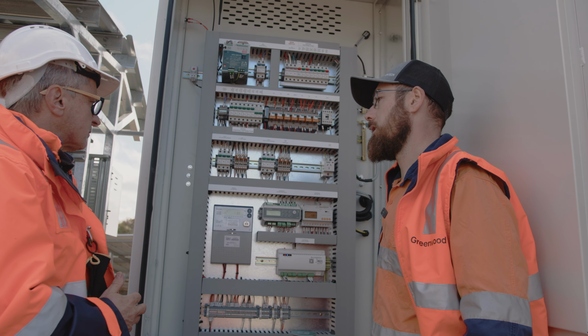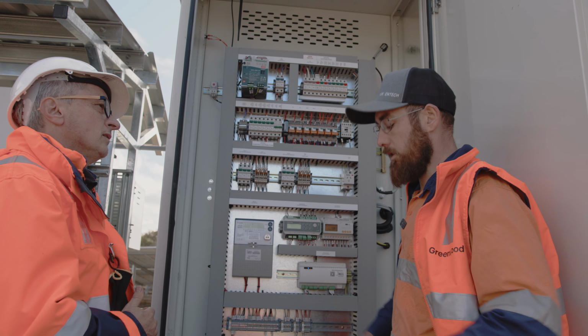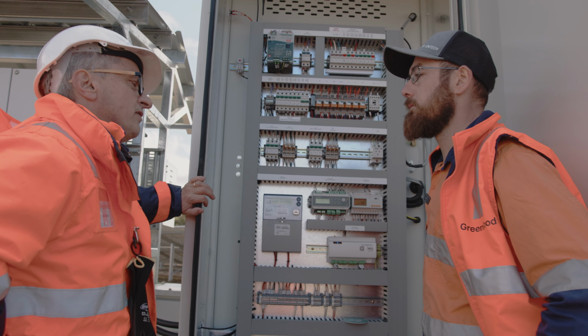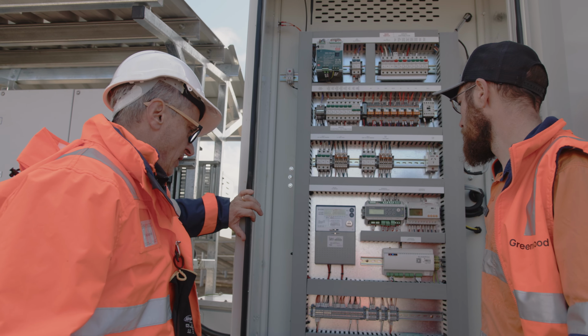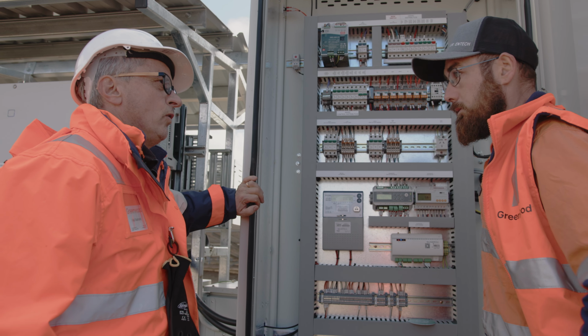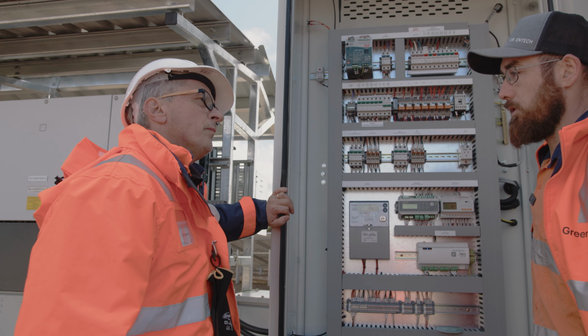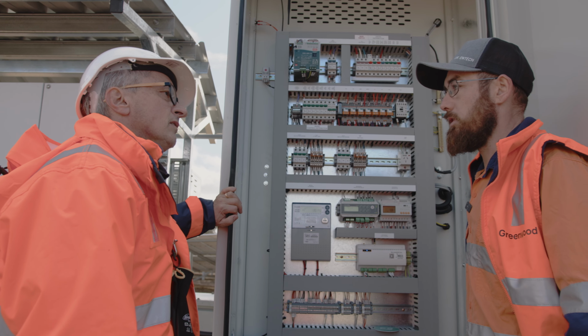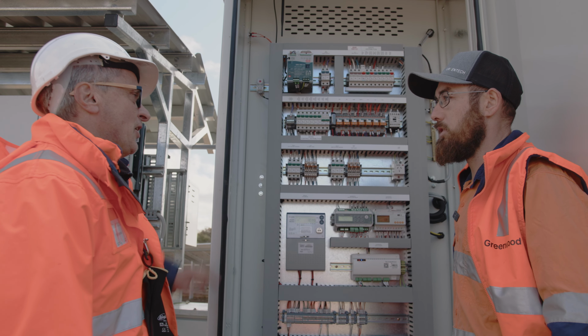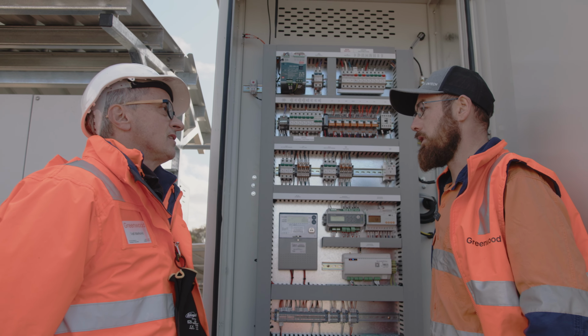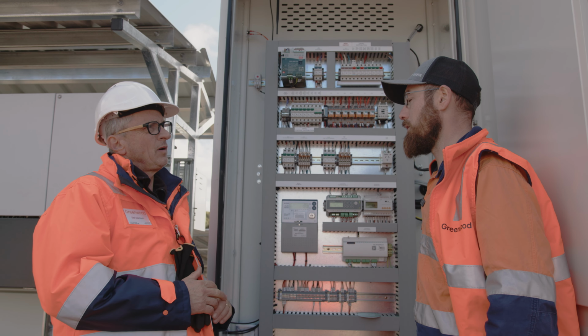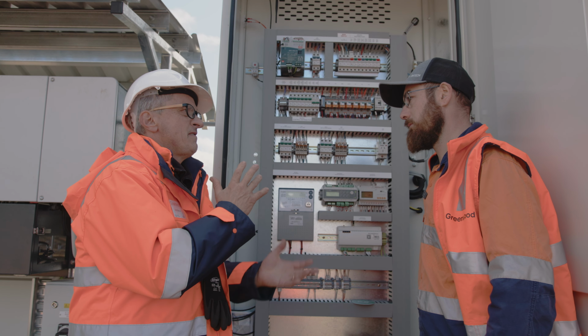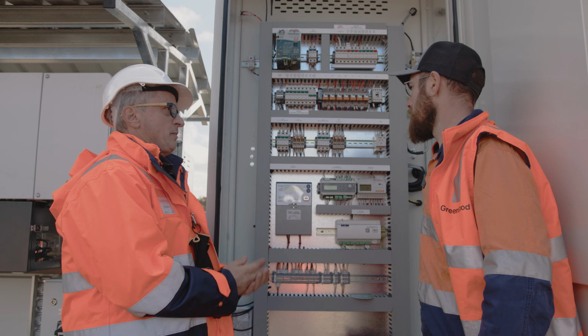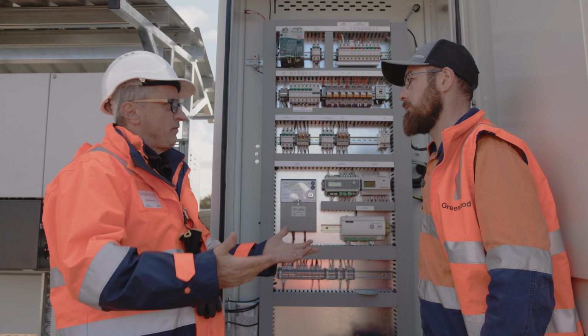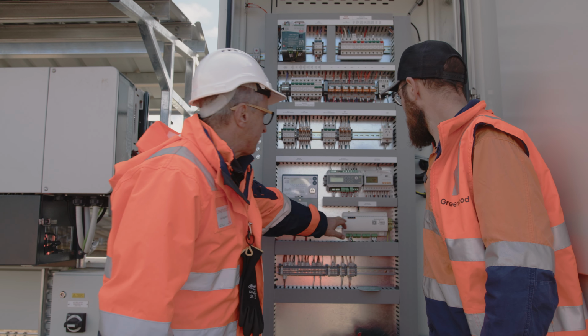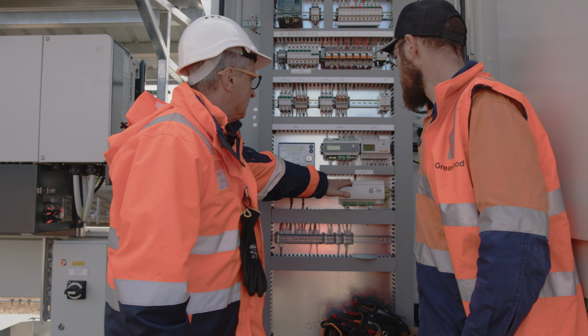Generally speaking, billing CTs are quite hefty. They're about this big each. So they don't use those, and correct me if I pronounce it wrong, Rogowski coil kind of stuff. They do not. Those are a split core CT. They use solid core. Because the accuracy between a split core and a solid core isn't that much different, but when you're talking about billing, it's significant. They have to be very, very accurate because at the end of the day, it's all financial, isn't it?